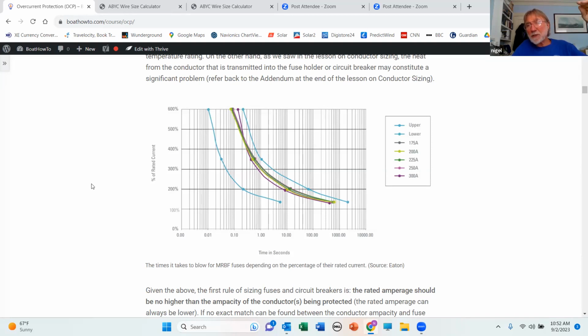But as the ambient temperature goes up, you lose that threshold. And the other thing that happens is, as the current goes up, let's say it goes to 300 amps, so we've got a sudden huge surge through the system, the fuse is going to blow quite quickly. And if we go to 1,000 amps, it's going to blow almost instantaneously. So we have this curve of time versus amps to see how quickly it will blow. On most of our boat circuits, we want what's called a slow blow fuse, which has a fairly slow curve to it, so that if we get sudden spikes through the system, it's not going to nuisance blow.